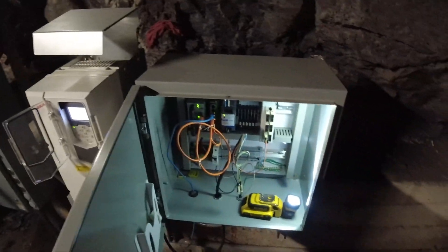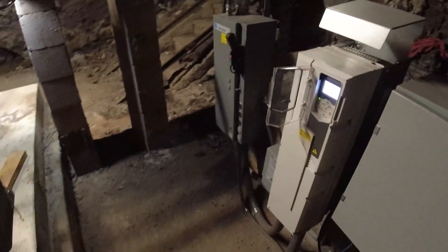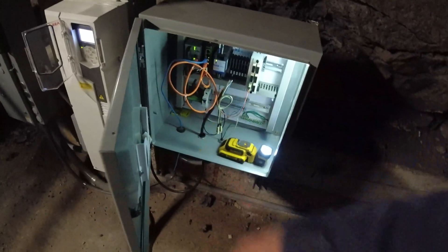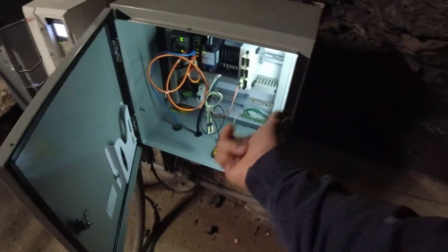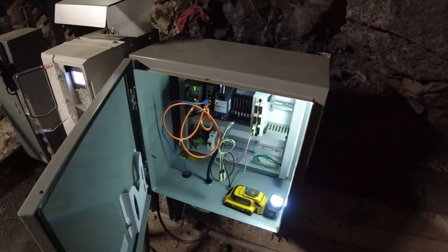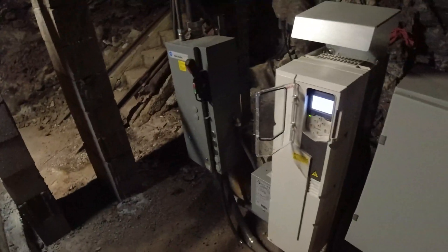At this point there's really not much else for me to look at here. Power supply is good, everything's good. I think I'm just going to chalk it up to some kind of power voltage anomaly, and I need to let the operator know how to open this up and check that - because this is too simple to warrant me or anyone from our company having to come here just to flip a breaker. If it keeps tripping or won't reset then it makes sense to send us out, but that's well within this operator's wheelhouse.